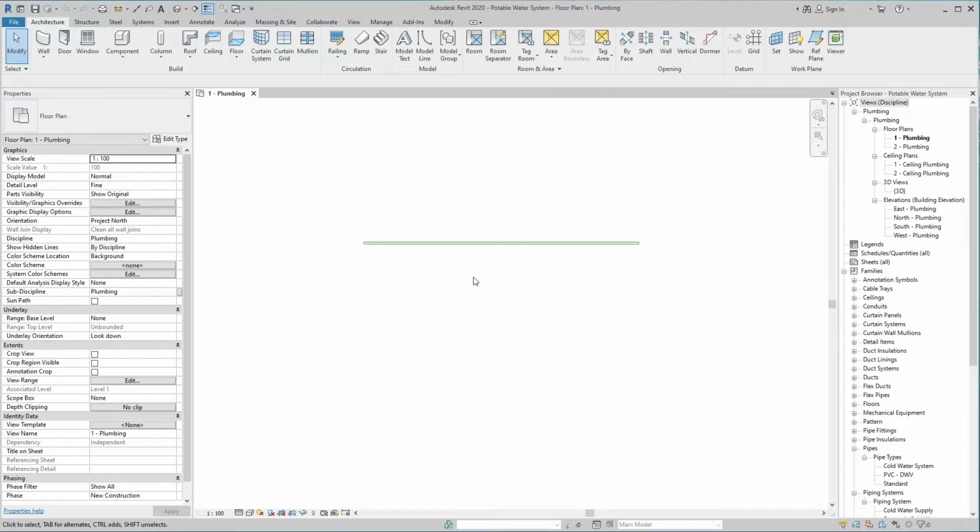Knowing the pipe material is very important for the piping system. For example, we need PPRC material for potable water system, UPVC for the sanitary system, MS seamless pipe for fire water system, and copper pipes are required for refrigeration system. This is called a pipe segment.